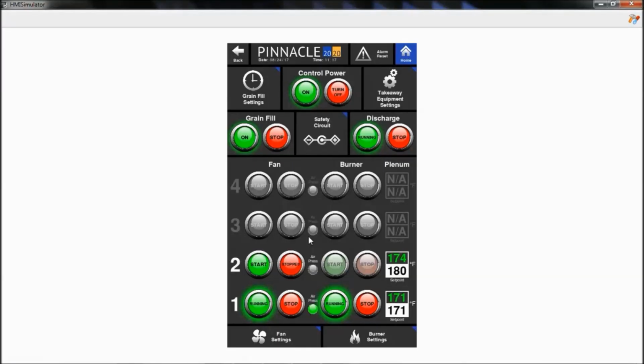Yeah, so it's scaled 0 to 60. We just don't allow you to go under 6 hertz, which is 10%. And then it's an easy calculation from there. So if you're running 50%, you're going to be running at 30 hertz. Yep.